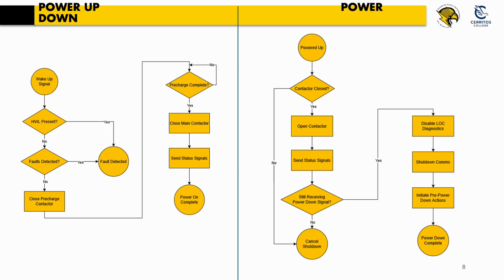From there, the software waits for the pre-charge phase to complete. Once the DC link voltage reaches 95% of the pack voltage, then the main contactor closes. The status signals are transmitted and the power on sequence is complete. Now, if we're going from a powered up state, we follow the powered down process shown on the right.